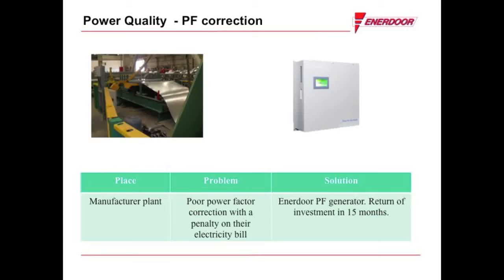After careful review, Enerdoor analyzed the facility's electrical bills for the past four to six months to help properly size a new static VAR generator, also known as an SVG. After installation, the Enerdoor SVG corrected the power factor in the factory, which in turn removed the additional reactive power line item charged to the end-user's power bill.